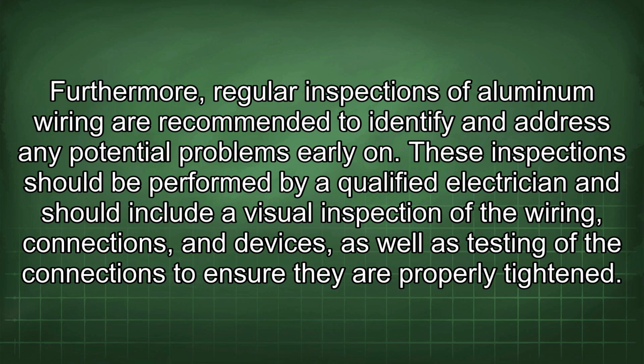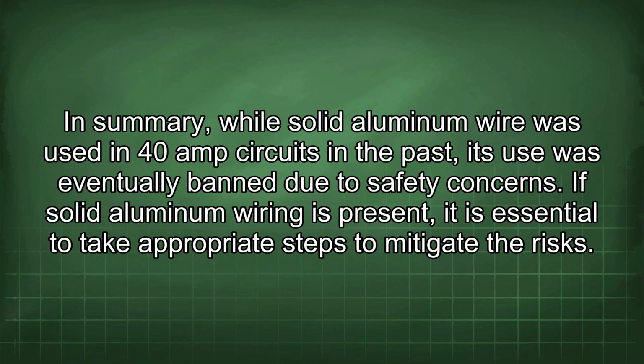Furthermore, regular inspections of aluminum wiring are recommended to identify and address any potential problems early on. These inspections should be performed by a qualified electrician and should include a visual inspection of the wiring, connections, and devices, as well as testing of the connections to ensure they are properly tightened. In summary, while solid aluminum wire was used in 40-amp circuits in the past, its use was eventually banned due to safety concerns. If solid aluminum wiring is present, it is essential to take appropriate steps to mitigate the risks.